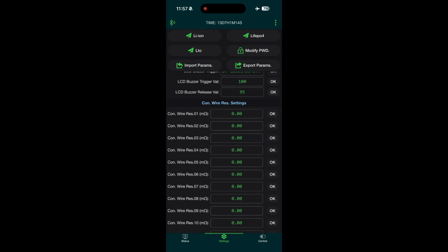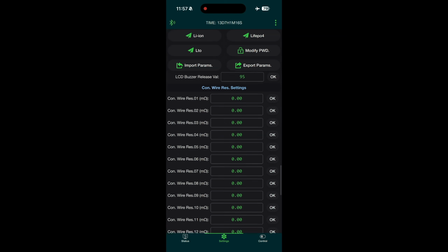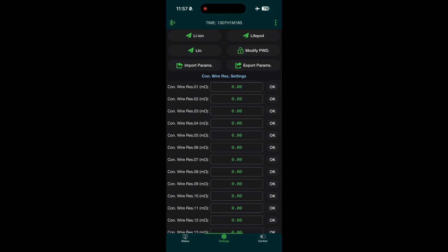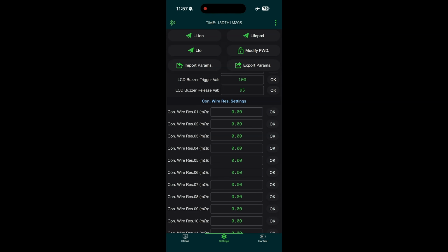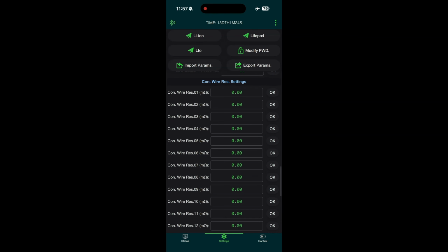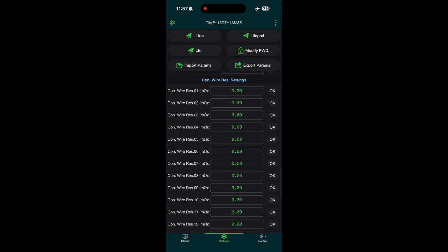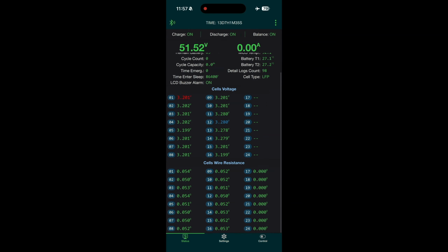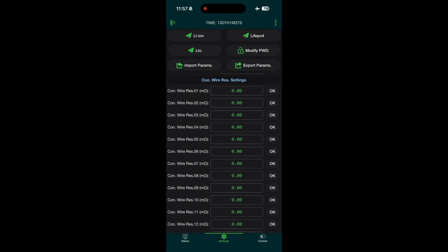Below that, we've got our connection wire resistance. As I mentioned at the start of this video, you can actually set or calibrate the resistance of each of the wires. I've never actually done it and never felt the need to. But if you measure your wires and find each wire has a different resistance value to what it shows on the home screen down the bottom here, you can go in and update that, and that'll help calibrate it.